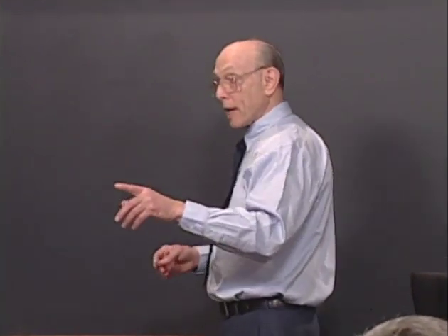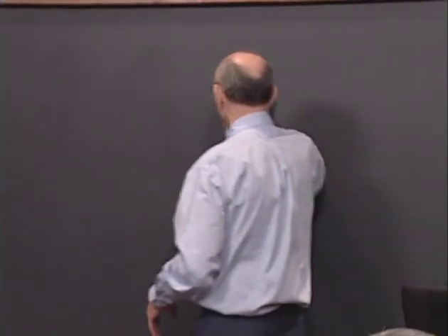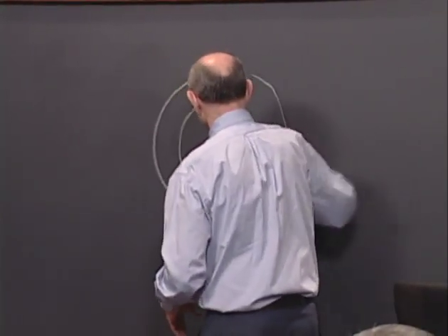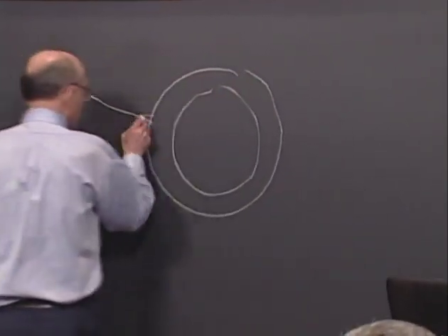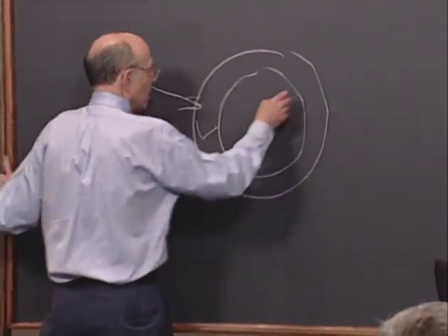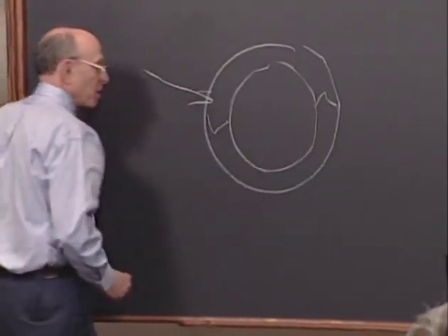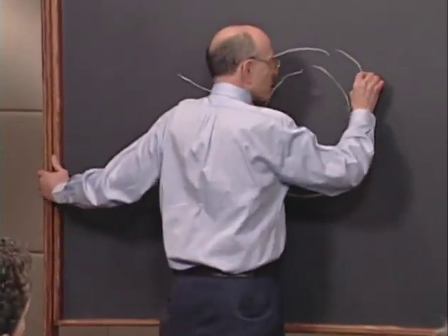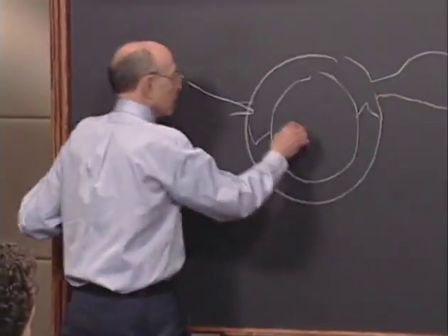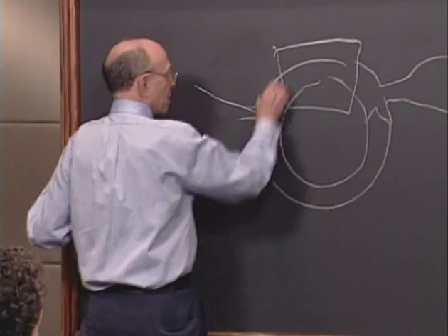So it's nice to have a reservoir bag or something on to perhaps deflect that flow. That's right. If you've got the reservoir bag on, even though you've got a high flow that you leave on all weekend, no problem. And that's because here's our circuit. Here's the gas flow coming in, and there are one-way valves. And here's our reservoir bag over here. And here's our absorbent here.